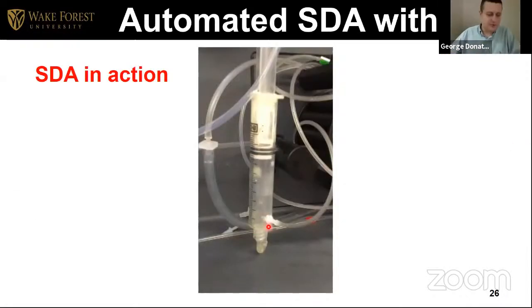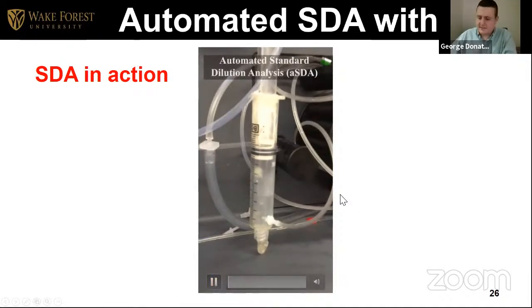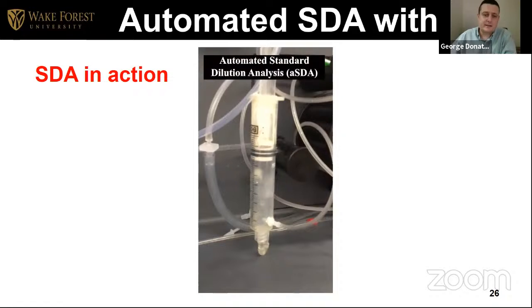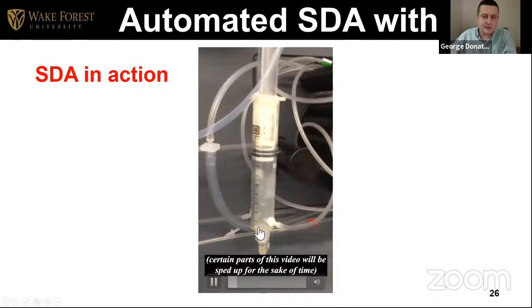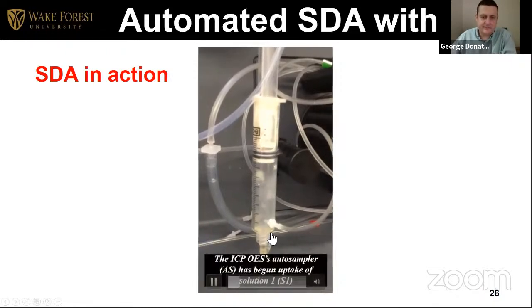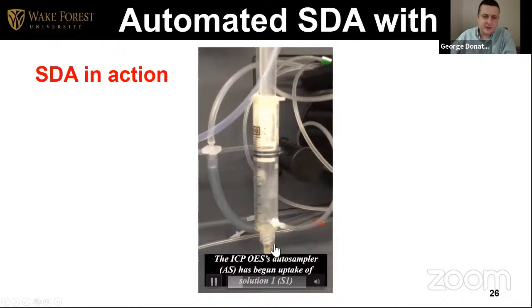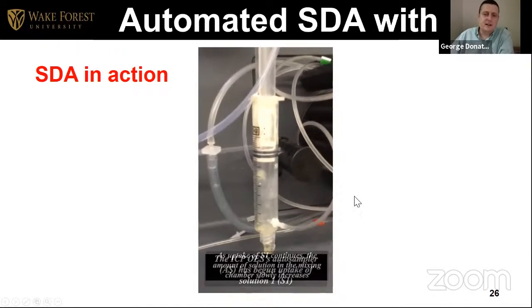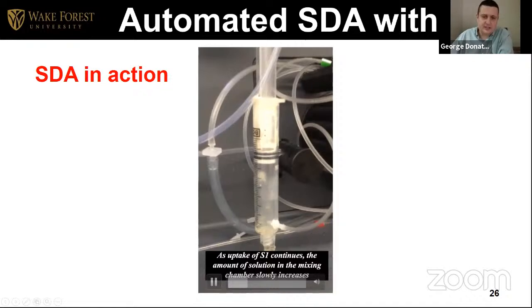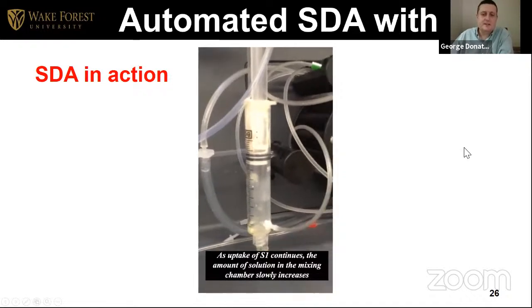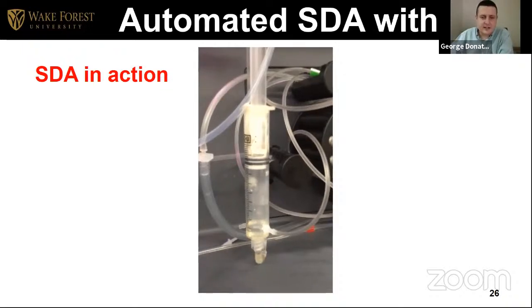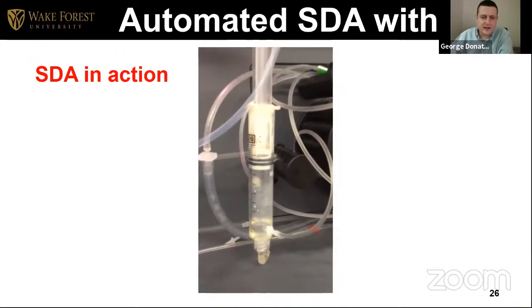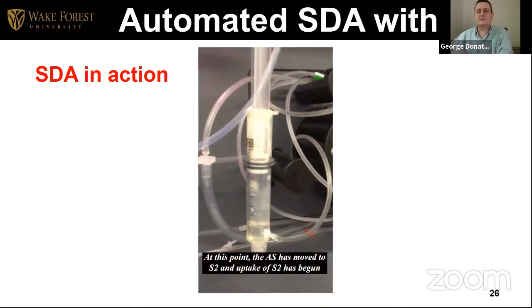Here's a little video so you can have an idea of how that looks in real life. You can see there sample 1 is getting into the syringe, and that syringe is going to fill up because of the difference in tubing size there, and it goes to waste, but it's going to fill it up. As it fills up, the sample will go out through here and go into the ICP. There's a little fast forward there, and the sample will start going through the ICP. As it goes through the ICP, that first part of the graph is taking place.